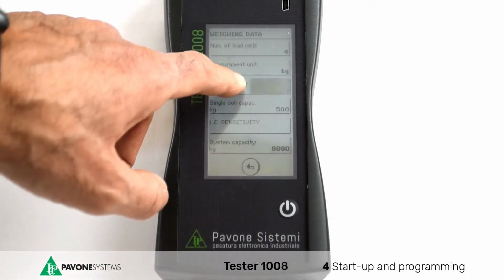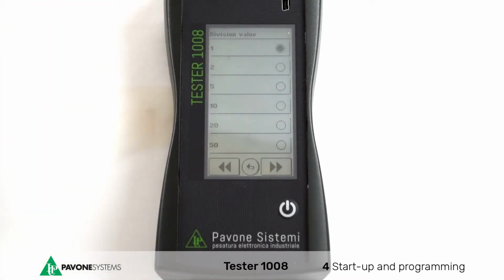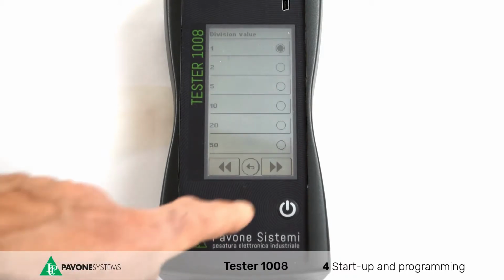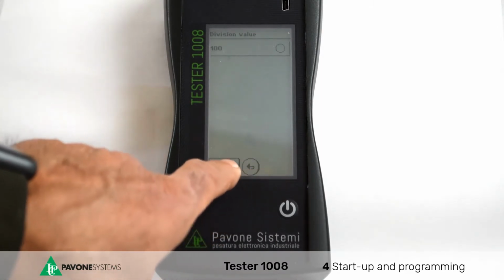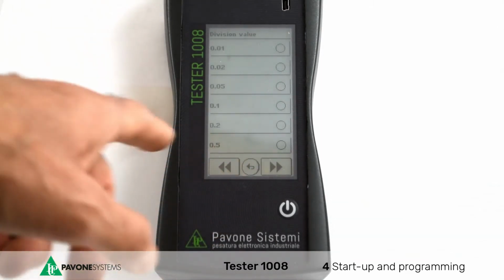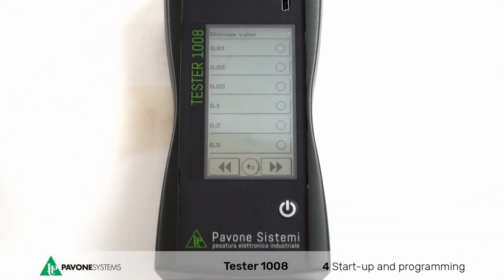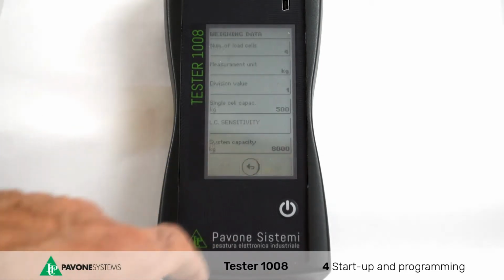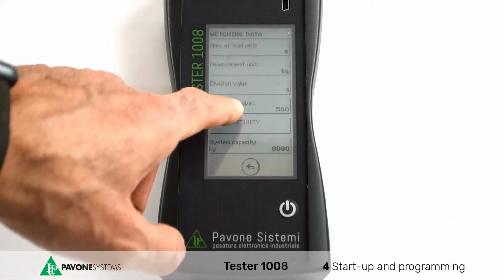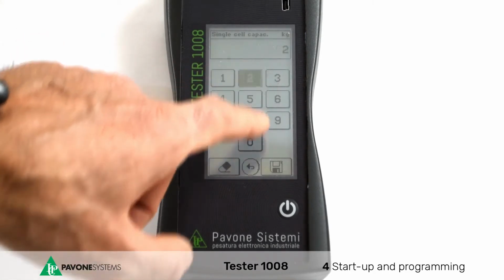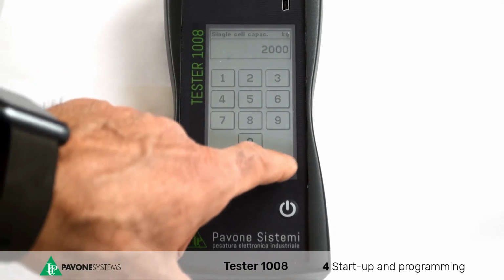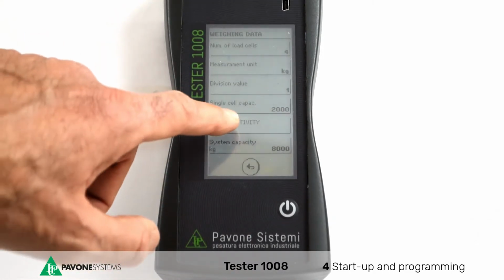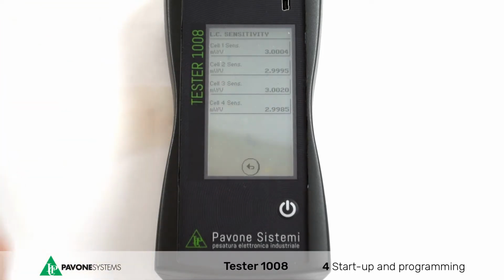Later, select the division value. This is the minimum weight variation that the display can show. Now, set the single cell capacity, which can be found on the nameplate of each individual load cell, in this example 2000 kilo.